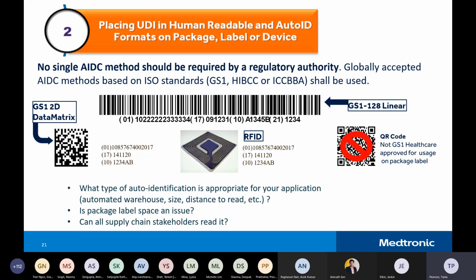As I mentioned before, the second part was about placing the UDI and the human readable and the AutoID formats on the package label of the device. One thing to note is that no single AIDC method should be required by a regulatory authority. It's globally accepted methods, and it's going to be based on the ISO standard, GS1, HIBCC, or ICCBBA. That's what should be used. But these are examples of some different formats.